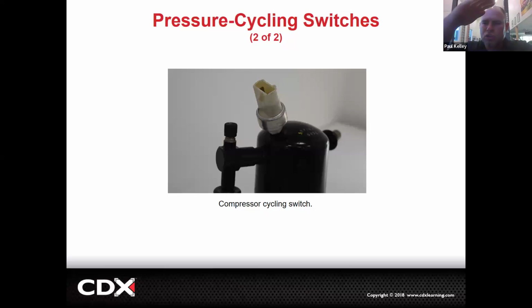And as it's back on, the low side pressure is getting low, low, low until it gets too low and it opens the contacts, which interrupts the power again. Makes sense? So that's why it's called a cycling switch. And the low side cycling switch, that's what it does.